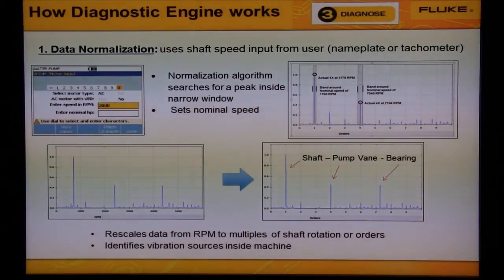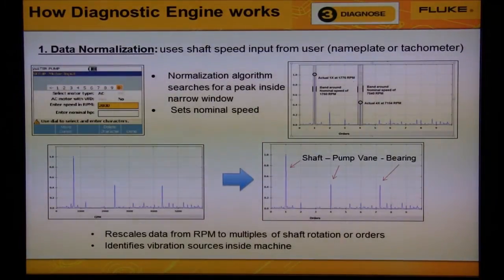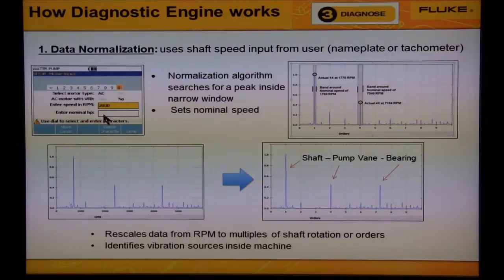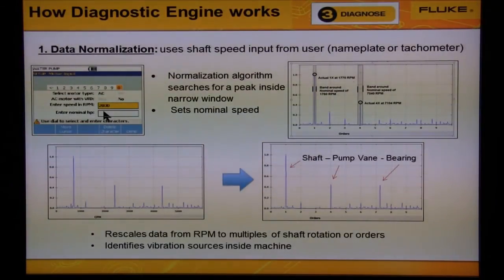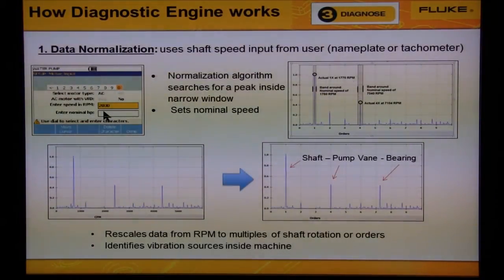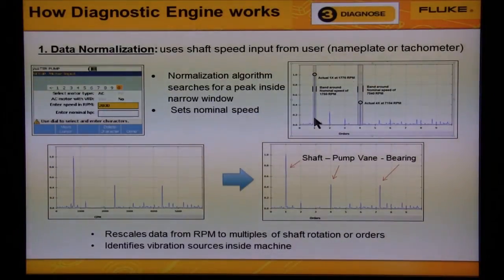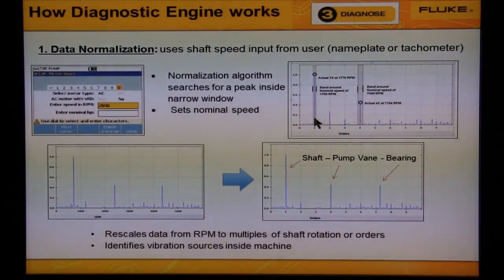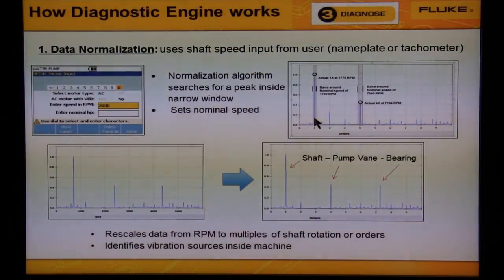In the first step, we need to find the actual speed of the rotating shaft. Based on the target speed given by the user during setup, the diagnostic engine looks for the largest peak inside a plus or minus 4% window. This is seen on the graph on the right.